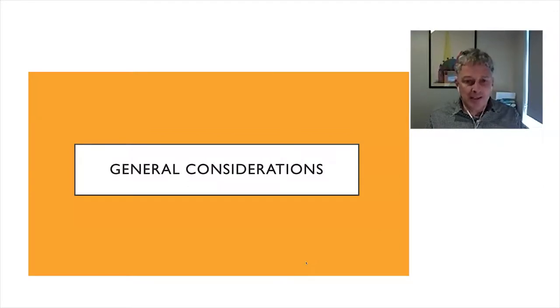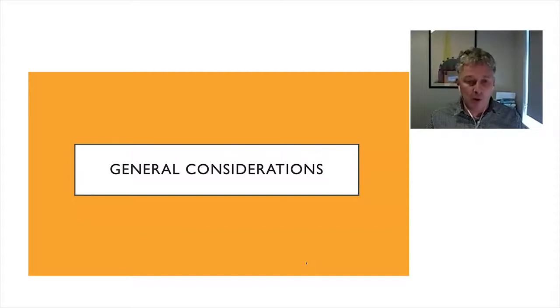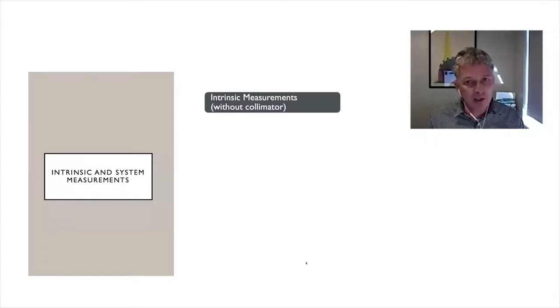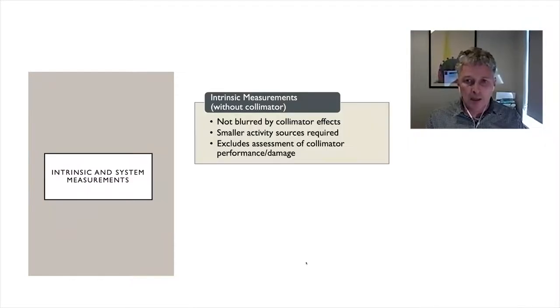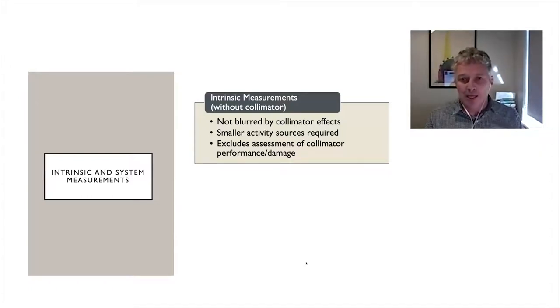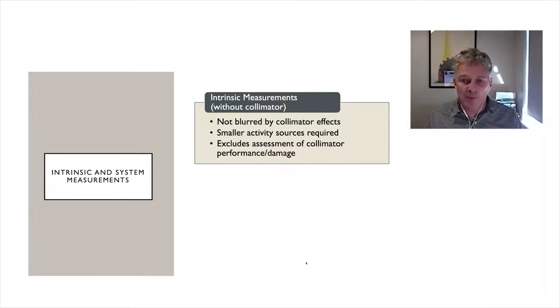Before going into detail, we need to consider some general considerations for how we set up acquisitions and processing for quality control. First, intrinsic versus system measurements. Intrinsic measurements are without the collimator, and they offer the advantage that the detector is not blurred by any collimator effects. So if we have non-uniformities, we're more likely to see them intrinsically. Intrinsic measurements also allow us to use smaller activity sources since there's no collimator in place.